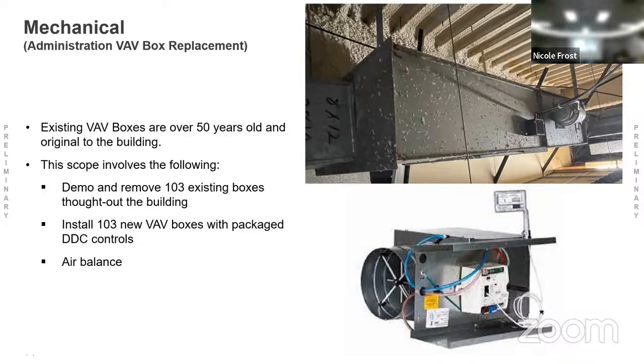Can you help me understand, when you were talking about the air handlers before, you said some were constant volume and weren't getting VAV boxes? There's 5 air handlers up there. 3 are bigger, and from the original design are piped to VAV boxes serving all 3 floors, kind of segmented by the building. There's 2 smaller ones - I think one serves just this room we're in now, so there's no boxes needed since it's only serving one space. That's a dedicated air handler going to one large room. I think there's one other one that serves the large meeting room below on the 2nd floor - those large meeting rooms have their own dedicated air handler serving just that one space. The VAV air handlers serve multiple spaces.